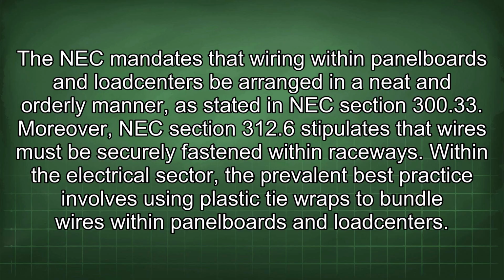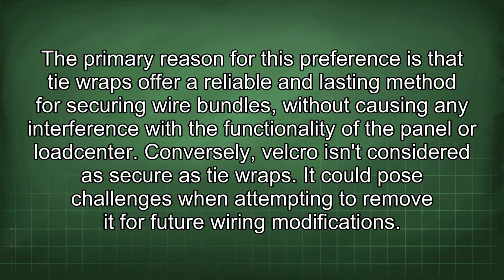The NEC mandates that wiring within panelboards and load centers be arranged in a neat and orderly manner, as stated in NEC Section 300.33. Moreover, NEC Section 312.6 stipulates that wires must be securely fastened within raceways. Within the electrical sector, the prevalent best practice involves using plastic tie wraps to bundle wires within panelboards and load centers. The primary reason for this preference is that tie wraps offer a reliable and lasting method for securing wire bundles without causing any interference with the functionality of the panel or load center.